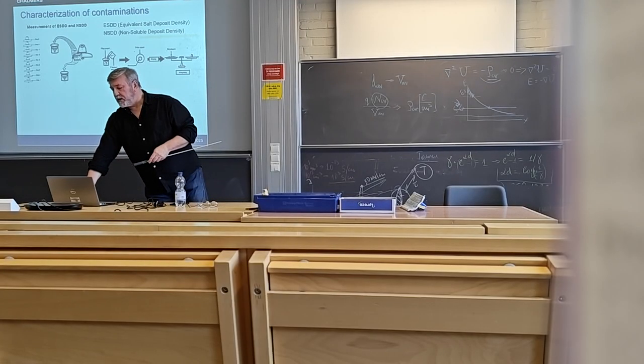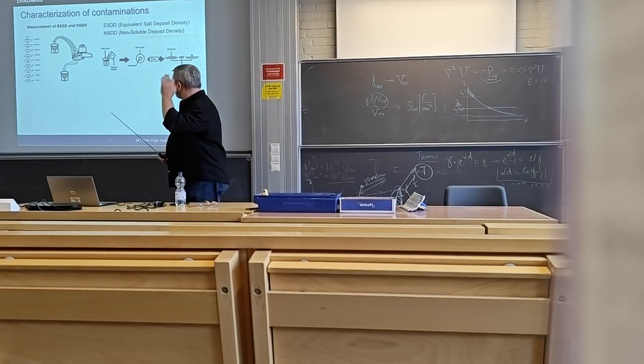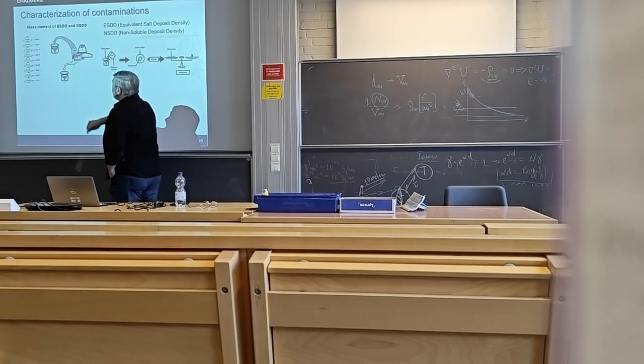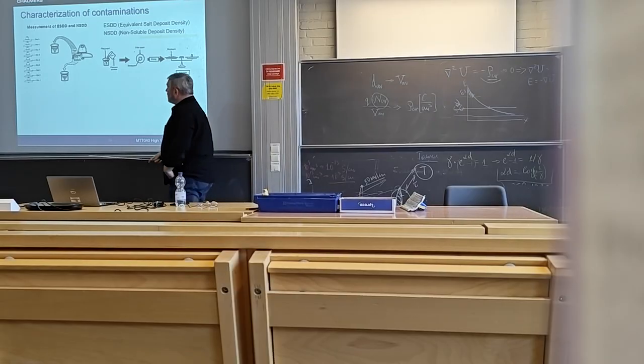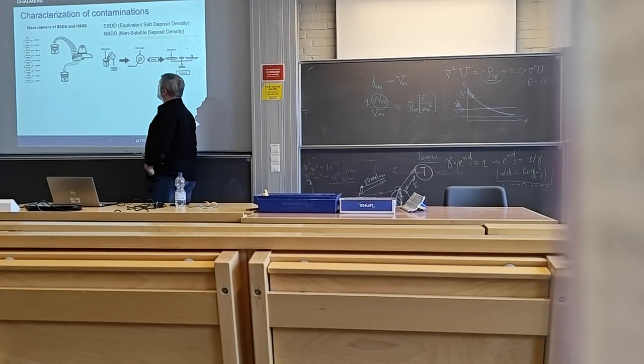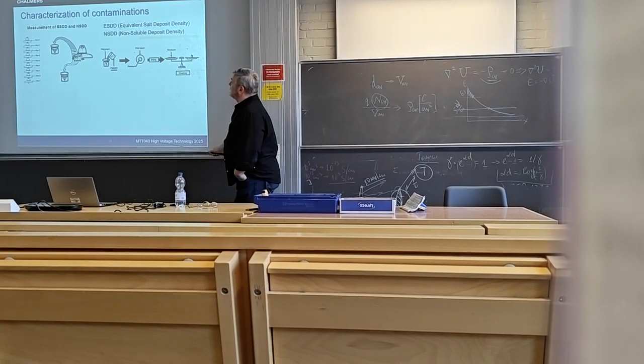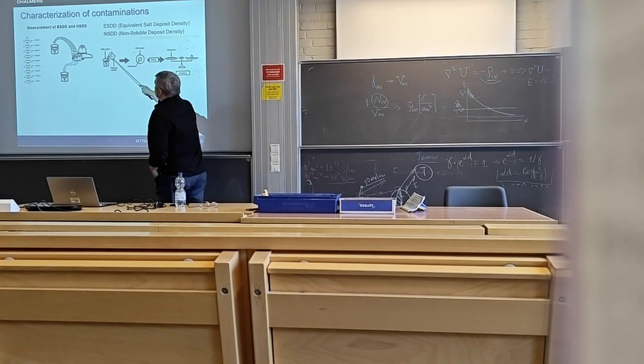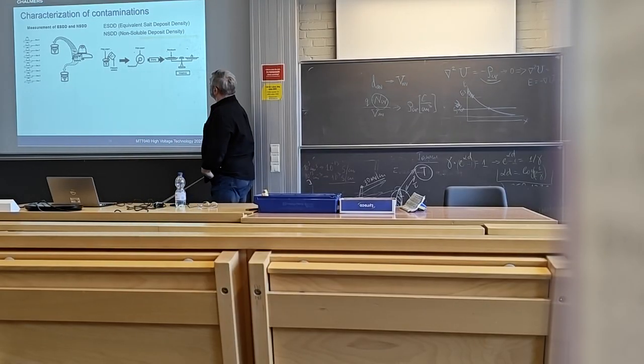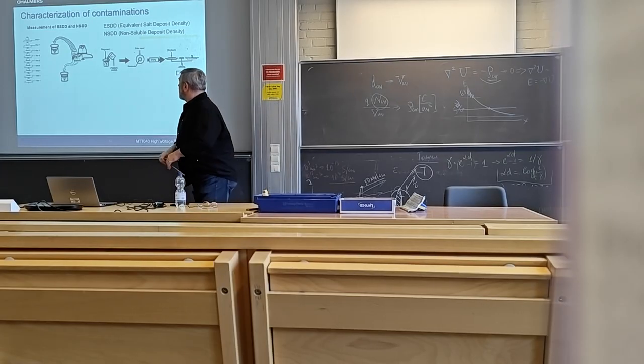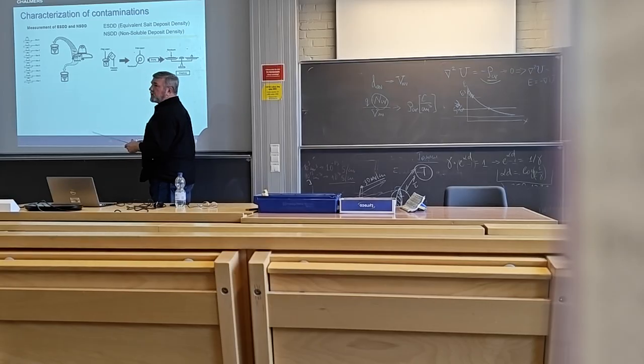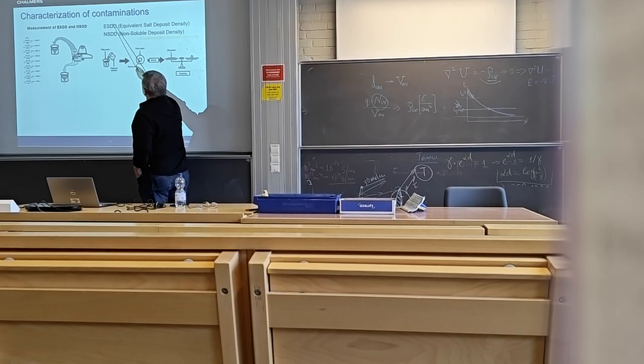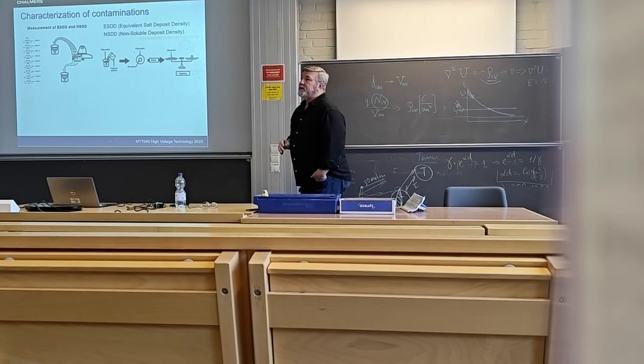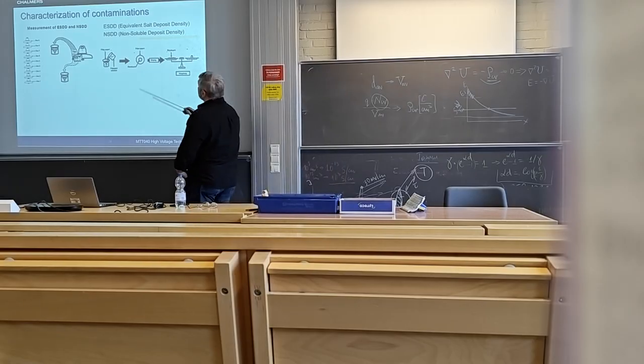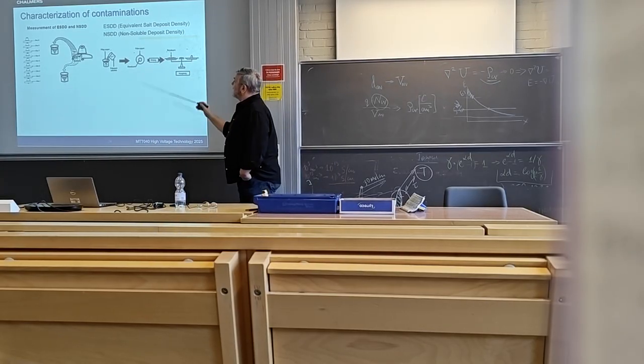Yeah, how do they characterize these pollutions? Basically, what people do is take an insulator from the string and wash it, separately washing the bottom side and separately washing the top side. Then they filter this water, get the residual, and dry it and weigh it. There are two parameters for evaluating the pollution density. One is called equivalent salt deposit density, ESDD, which is more or less for soluble pollutions, and the other is non-soluble deposit density, NSDD.